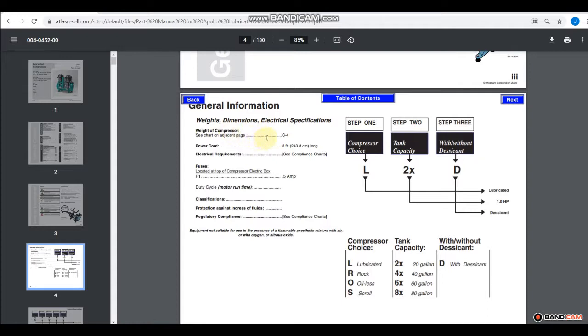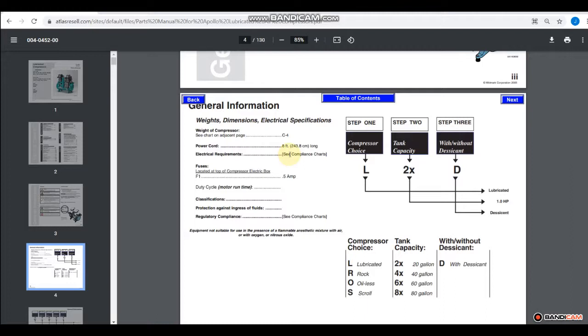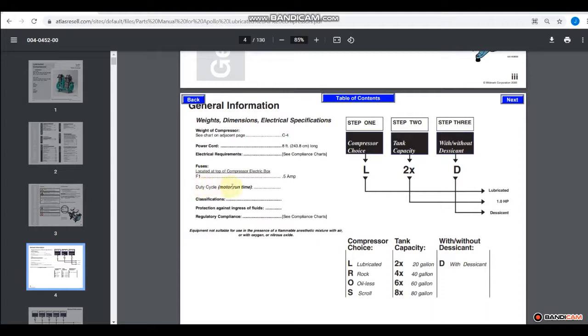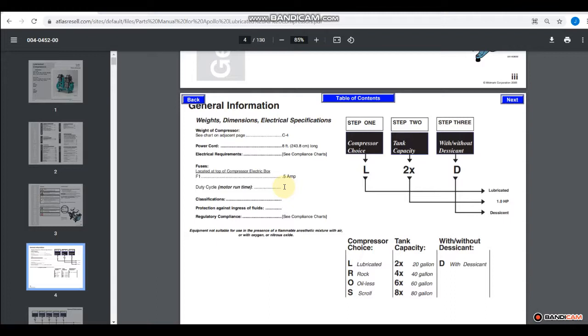So there is a weight chart that's on the next page. The power cord is typically eight feet. The electrical requirements are going to be based on the compressor itself. There's definitely a voltage requirement as well as an amperage per head, and that also factors into circuit breakers and sizing these compressors. It's important that you make sure you have the proper protection. There is a half amp fuse, which is F1, and the motor runtime is going to be based on the actual size of the tank itself and the amount of motors that it has, the compressor heads, to pump up the cylinder.